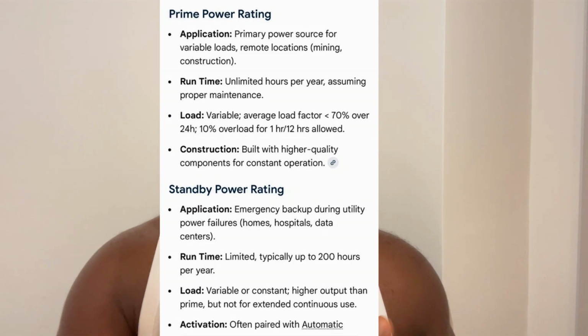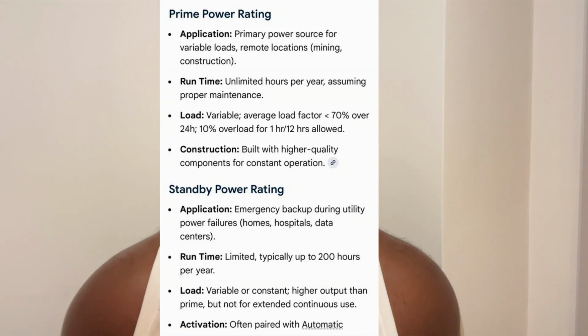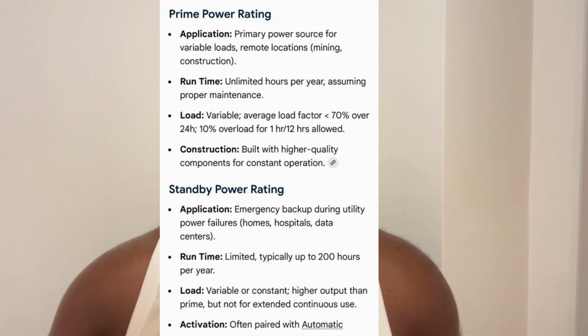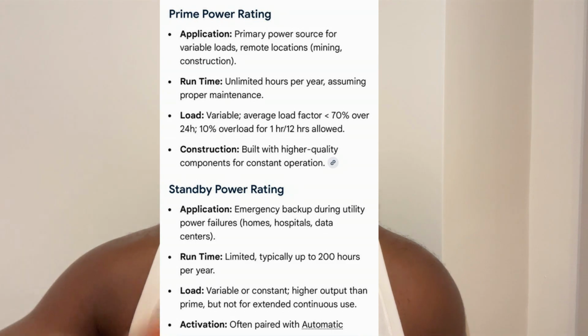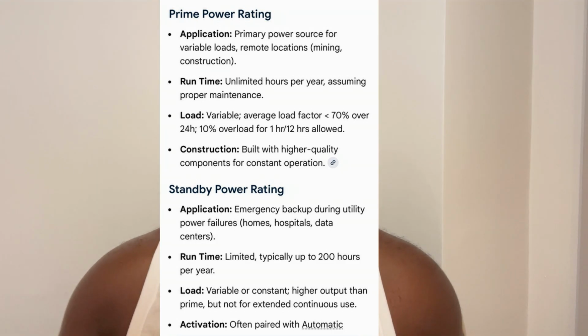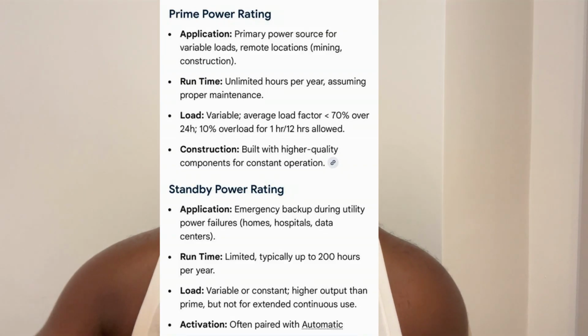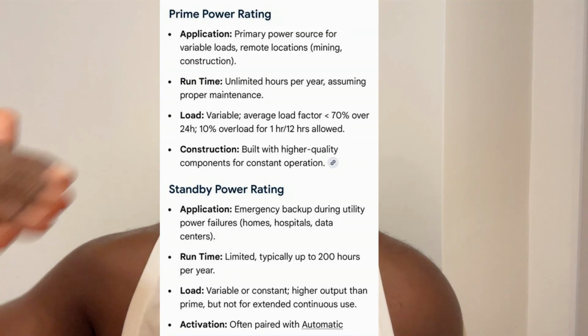So for example, let me give a quick definition. A standby generator, also called an emergency generator, is designed to support your home when you have a mains power failure. The components are designed to give you between 200 and 500 hours per year of runtime, whereas a prime rated generator can give you an unlimited number of hours of operation per year.